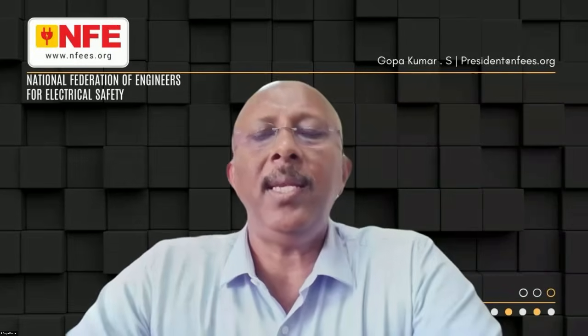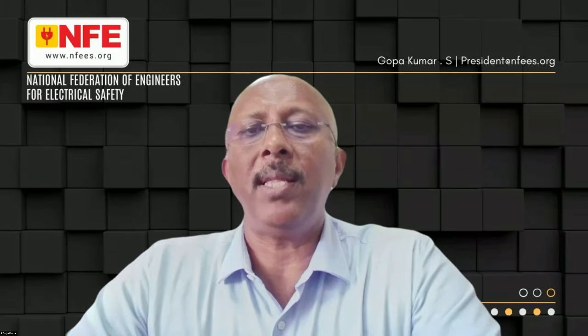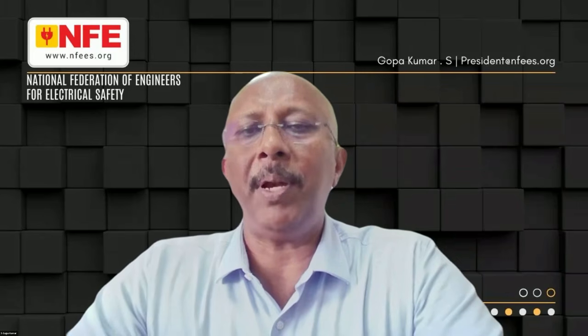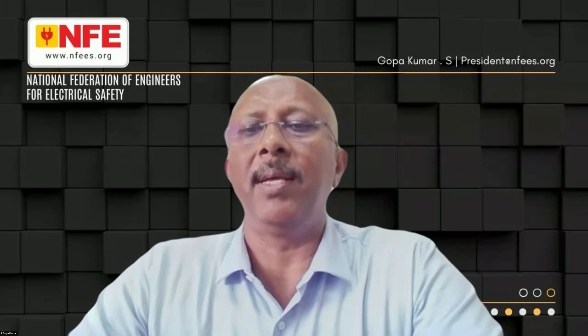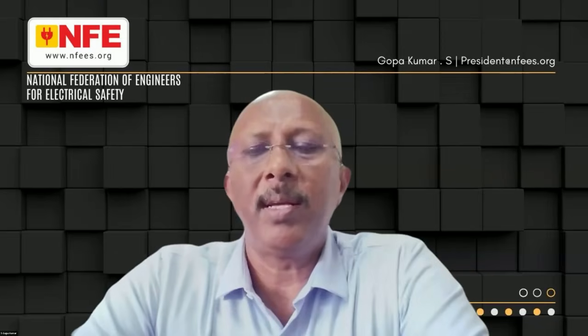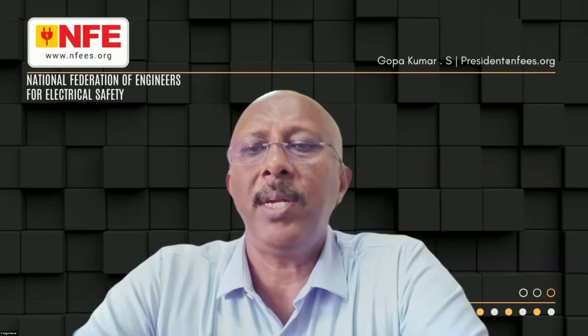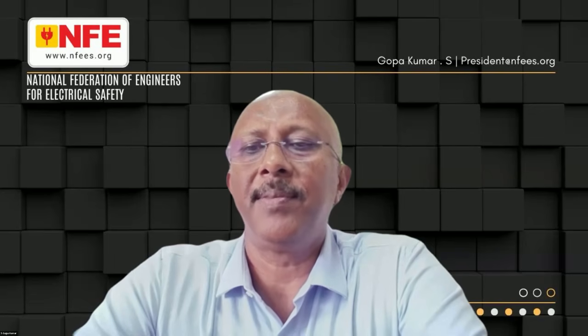To make a TT, the earth electrodes of the source and the distribution should be electrically separate, meaning 10-15 meters away. Practically, this may not be possible. And even in the disconnection times in the presentation, TT is not shown, sir. Only IT and TN is shown. Correct, that is why I had a doubt, sir. Because more and more, TNS for a normal location, IT for medical IT.